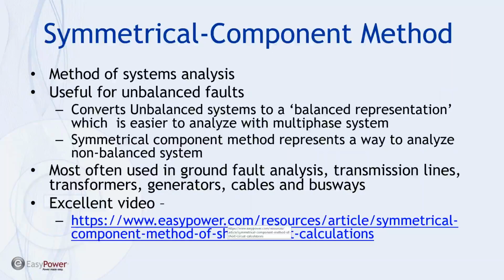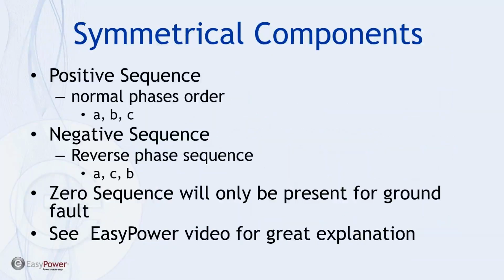We have a very excellent video on this on the website, and for a much more extensive discussion of the applications and the derivation, I would refer you to the EasyPower website. Just look up the symmetrical component video, and you'll find a very excellent discussion. But basically, when we're talking about symmetrical components, the system develops a positive sequence, which is referenced to the normal phase order A, B, C, and then a negative sequence, which refers to the reverse order, which would be A, C, B, and then the third symmetrical component is the zero sequence, and there we only see evidence of that being included when we have ground current. And so that's why this particular application is extremely useful in ground current applications and transmission lines where you're worried about ground faults.